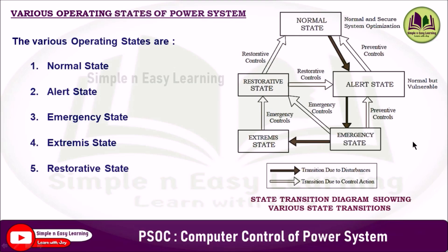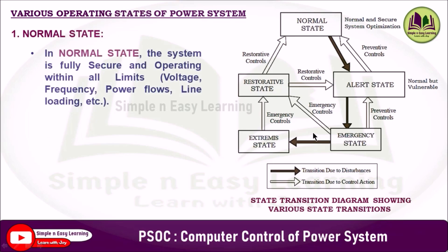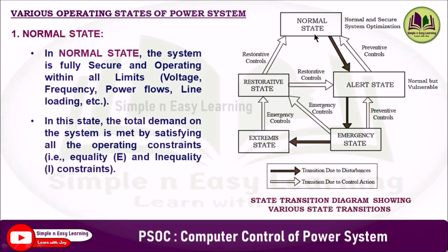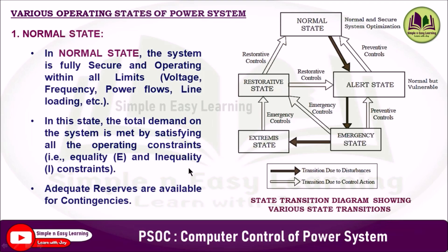In the normal state, the system is fully secure and operating within all limits — for example, voltage, frequency, power flow, and line loading. The total demand is satisfied while meeting all operating constraints: equality constraints (total power generation equals total power demand plus losses: PG = PD + PL) and inequality constraints such as generator capacity constraints, voltage constraints, spinning reserve capacity constraints, transformer tap settings, transmission line constraints, and network security constraints.